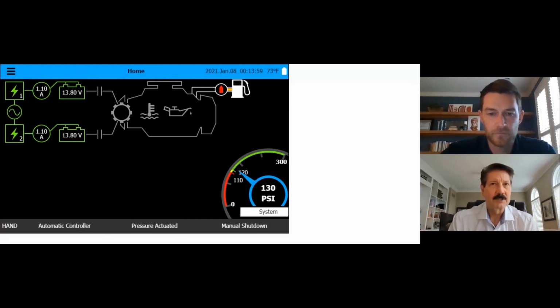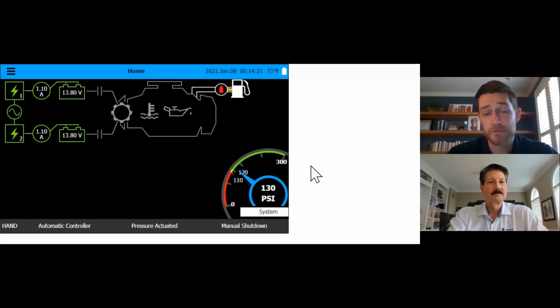Yeah, I mean, float charge could be anything, even up to half an amp, 500 milliamp. Bulk could be up to 10 amps. Right, depending on what the batteries are needing, and that's a code requirement. The chargers need to be rated for 10 amps anyway. So if it's stuck in that mode constantly, then it's most likely you have something wrong with the batteries. But it's just something to pay attention to. It will be on the screen, this being the home screen, so you can see if it's in bulk mode constantly. And then you have the two battery icons, showing that the voltage is healthy. That's why everything is green.